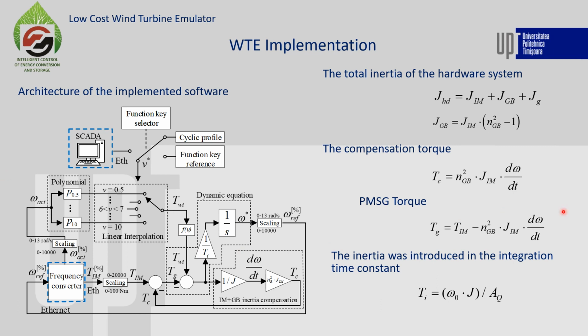Why was it necessary to introduce the time integration constant? Because it is not possible to divide the difference between the wind turbine and generator torque by the inertia before the integrator, since at low values the results will be imprecise when working with integers. Dividing after the integrator is also not a solution, because the maximum value of the integrator on this chosen intelligent relay is 1000, which would give a calculated reference speed of 7.06 radians per second instead of, say, a minimum of 10 radians per second, which is the rated speed of the wind turbine.